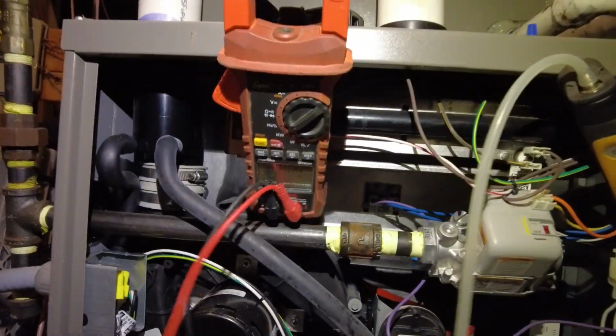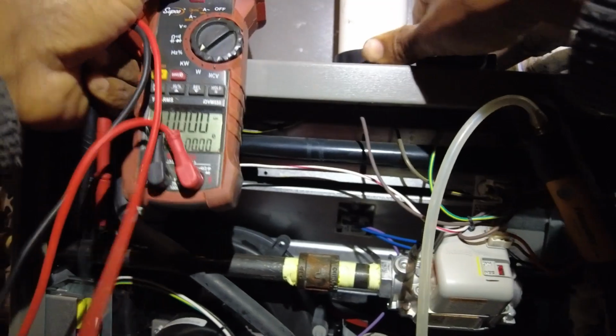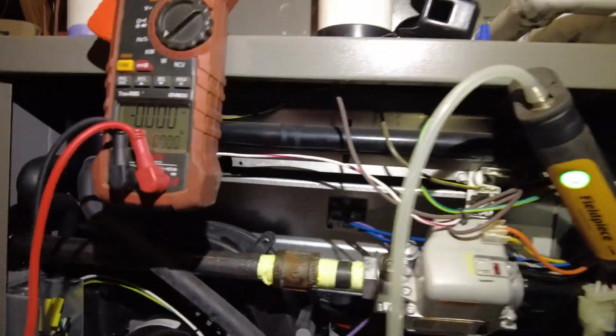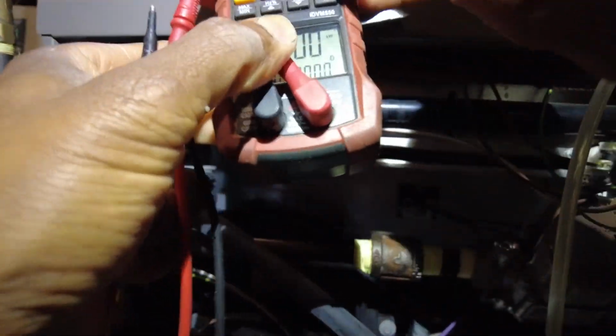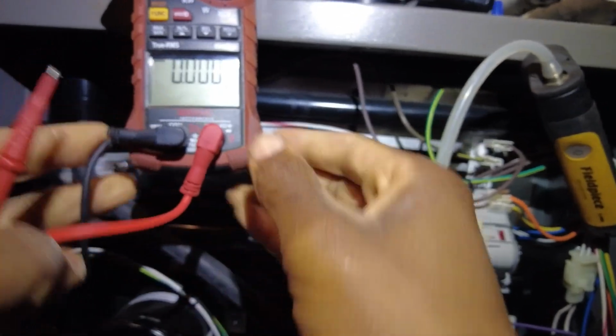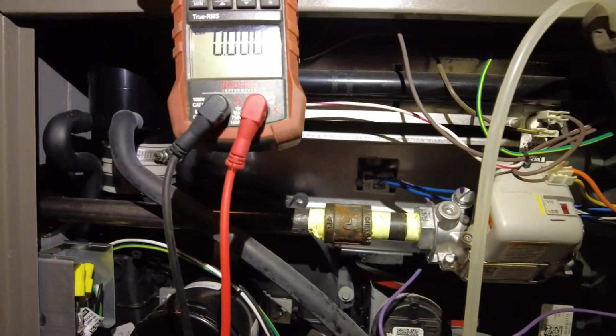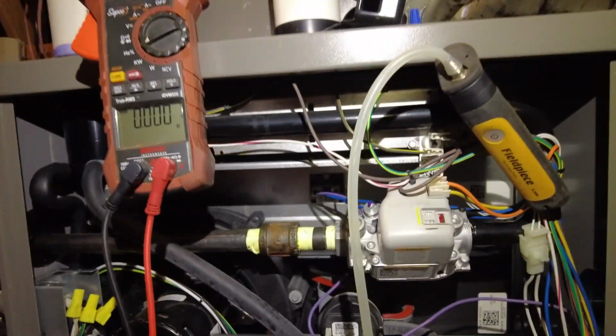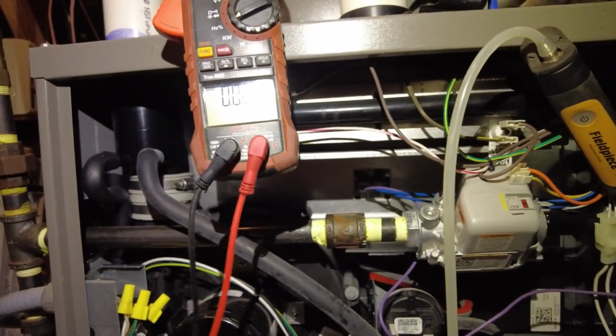If this is an ECM motor, then we're going to have to figure out something to mitigate that bypass. Either repair it so it's not slipping or sticking, or maybe do a dump zone, where it's not just cycling back into the return but dumping somewhere in the house that's not as critical. The reason being, ECM motors are a lot more vulnerable to high static pressure conditions. But if this is a PSC motor, then we'll be fine just letting it do its thing.